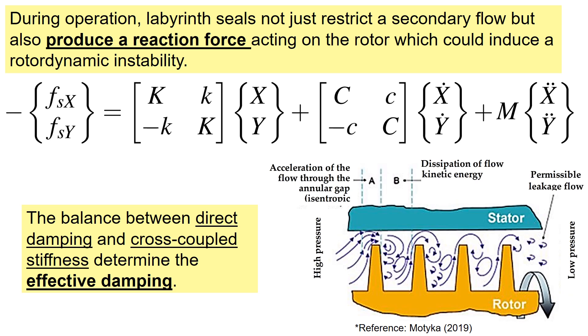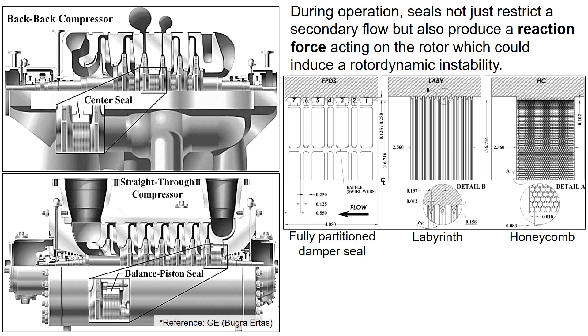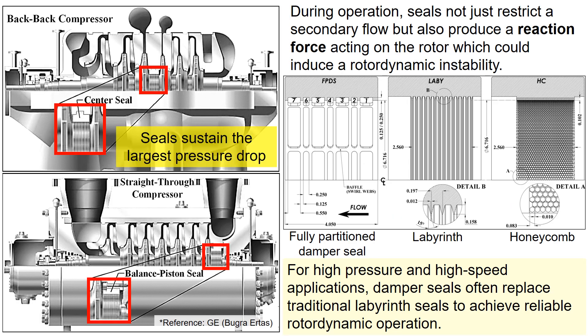The balance between direct damping and cross-coupled stiffness determines the effective damping. To achieve reliable rotor dynamic operation in high-pressure, high-speed applications, damper seals often replace traditional labyrinth seals.